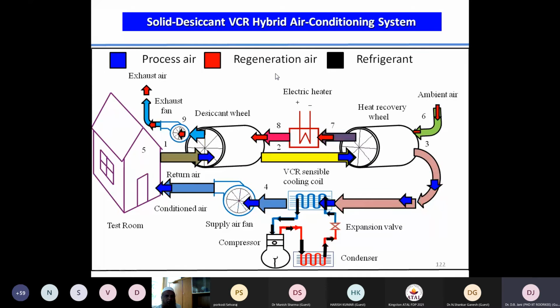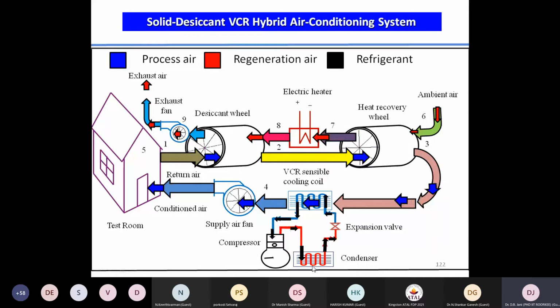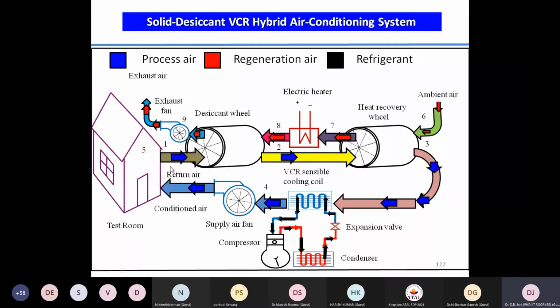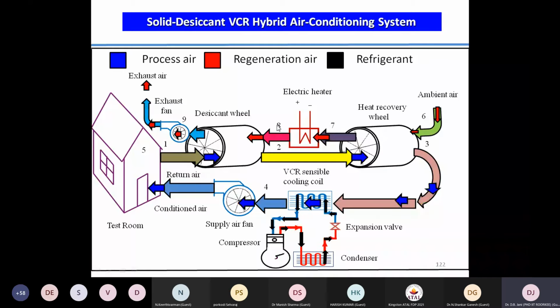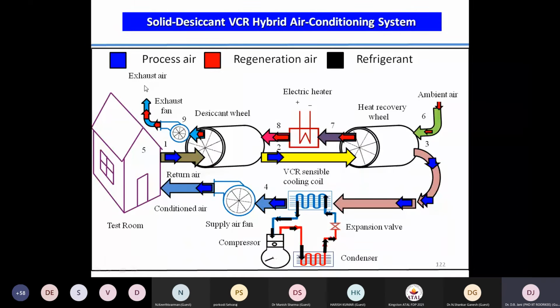The black color shows the flow of refrigerant through the conventional cooling mechanism, and blue shows the flow of the return room process air. The reactivation side is shown in the red area. After passing through the heater, the required temperature is maintained at the dehumidifier inlet on the regeneration side, and at the exit the air flows to the exhaust. The dehumidifier wheel speed is very low, around 20 rph, as compared to the heat recovery wheel as well as the other pumping mechanisms.